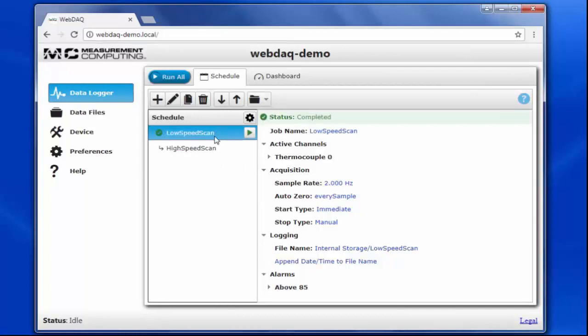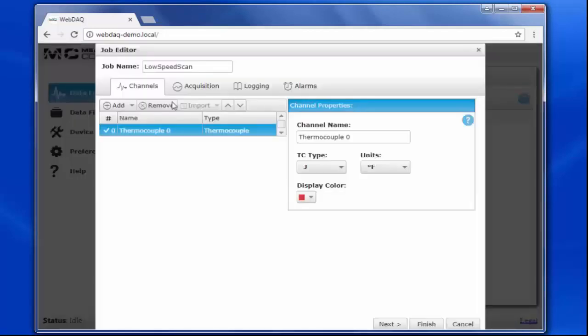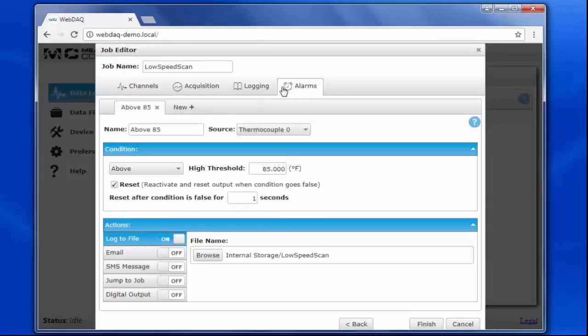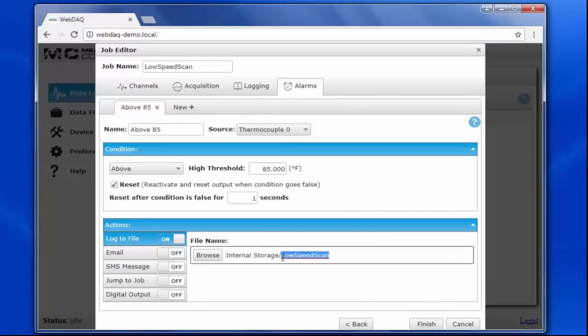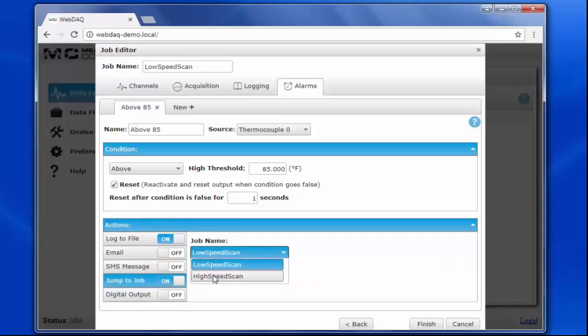I still need to modify my first job's alarm conditions to match. Let's go back to the settings for Low Speed Scan and change the alarm conditions. I want to log this alarm to the same file I set in High Speed Scan, Switch Jobs on Temp Limit. And again, I'll add an alarm action to jump to the job, High Speed Scan, when the temperature is above 85 degrees.